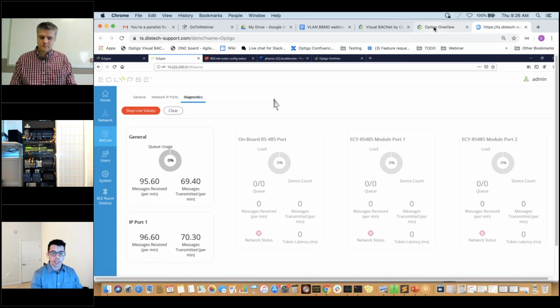And then you'll have to have a BBMD, or ideally a foreign device. Because if you just have one controller that has one value you need, you really want to set that up as a foreign device and have that go to the BBMD so that only its traffic is sent. And then you can, say, broadcast that value, which is my personal preference.